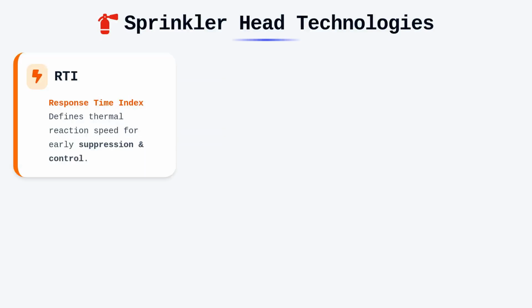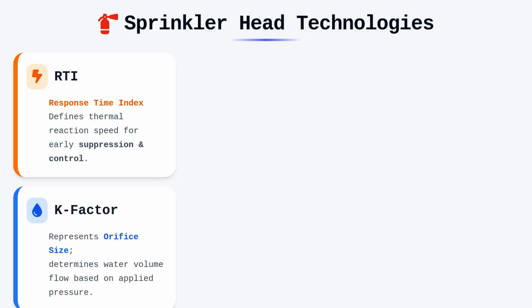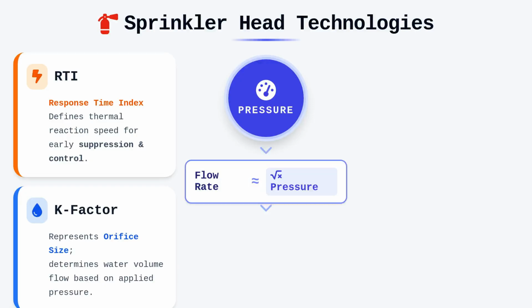When we inspect sprinkler head technologies, it is helpful to view them as a component with specific performance characteristics. The response time index, or RTI, defines how quickly the thermal element reacts to heat, which is critical for early suppression or control. We also use the K factor to calculate discharge. This value represents the orifice size of the sprinkler and determines how much water flows at a given pressure. If you increase the pressure at a sprinkler, the flow rate increases according to the square root of that pressure.